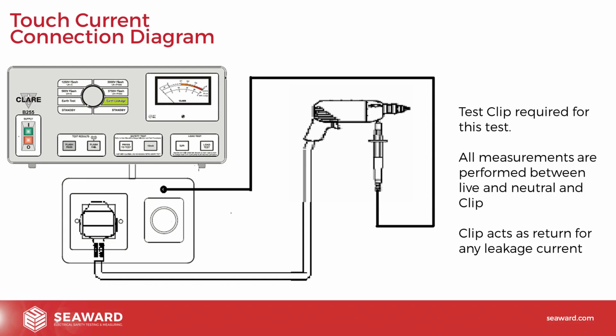With the B255, we have to move the probe or the clip around the unit. So we're going to be using on a B255 the same green cabled clip that we use for the earth test. The difference is we have to take the clip or the probe from the back of the unit, where the plug hits the back of the B255, we have to remove it from that point, and we simply move it to the front on the output box. You'll see there's a green 4mm socket. So we need to put the clip into that 4mm socket and then onto any exposed metalwork on the device that we're testing. And it's important to do that to ensure you get the measurement through the body model, and therefore we get a representative test.